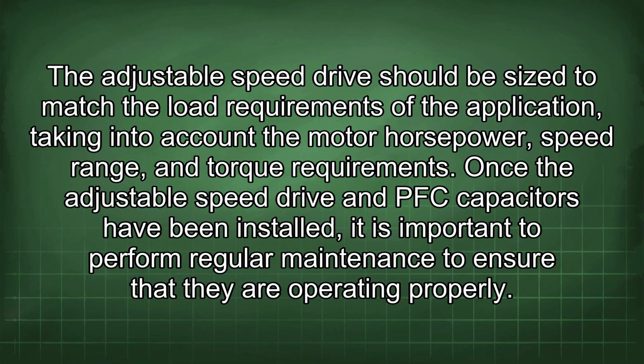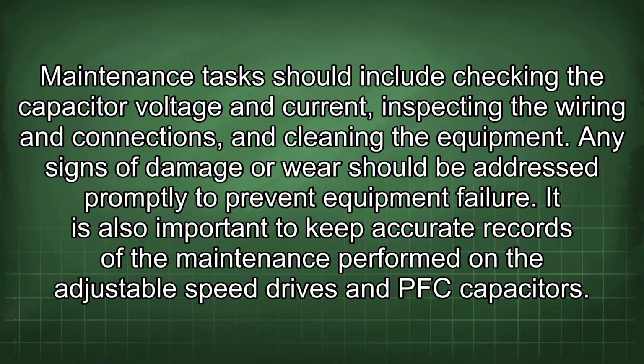Once the adjustable speed drive and PFC capacitors have been installed, it is important to perform regular maintenance to ensure that they are operating properly. Maintenance tasks should include checking the capacitor voltage and current, inspecting the wiring and connections, and cleaning the equipment. Any signs of damage or wear should be addressed promptly to prevent equipment failure.